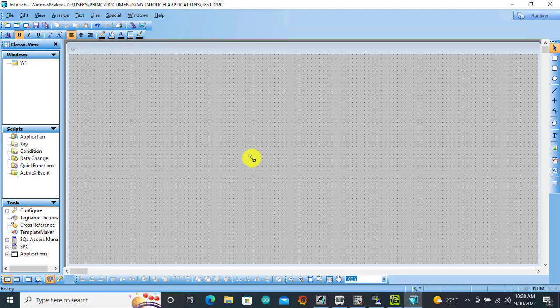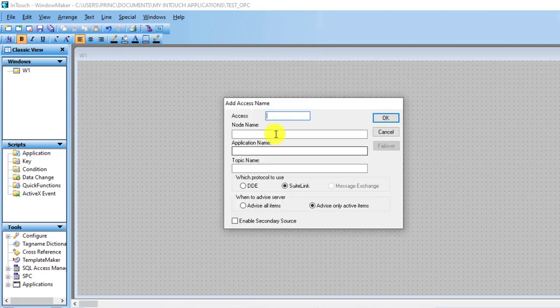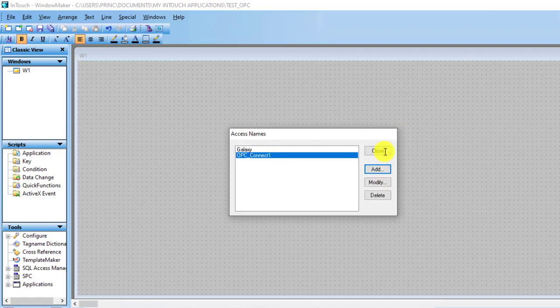With our window created, we now have to create a link between the software and the OPC server. Go to Special and then Access Names. We create our access name — click Add. For the access name, give it the same name: OPC_Connect_One. Under the Topic Name, also OPC_Connect_One. Here you need to specify the application as Server_Runtime. Click OK — our connection is created.